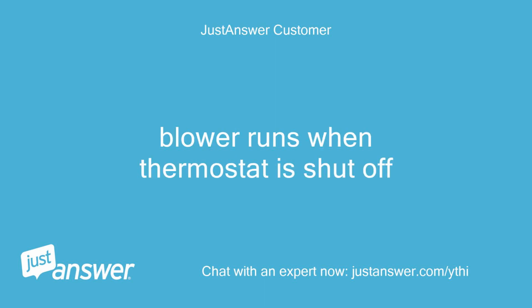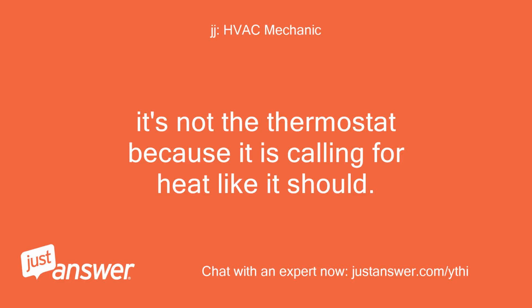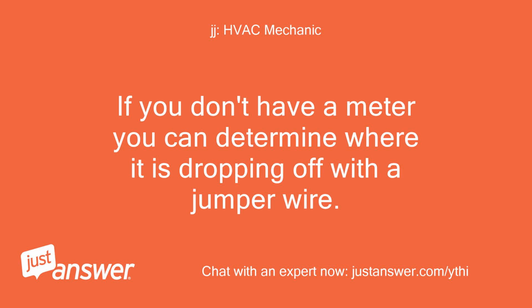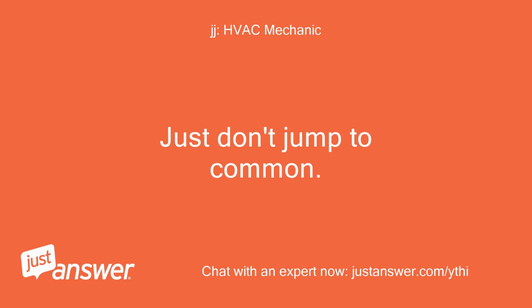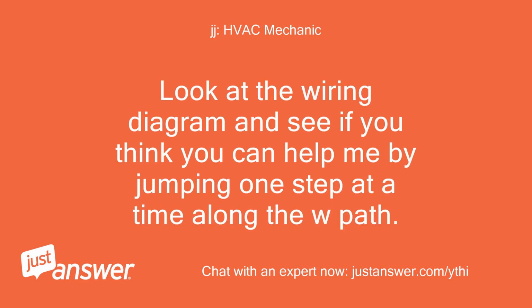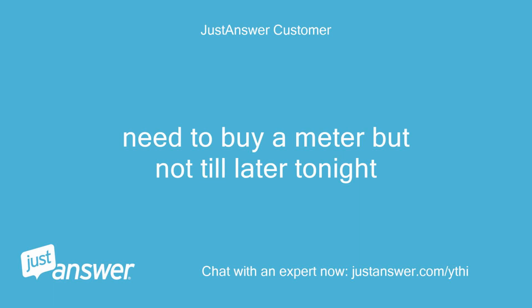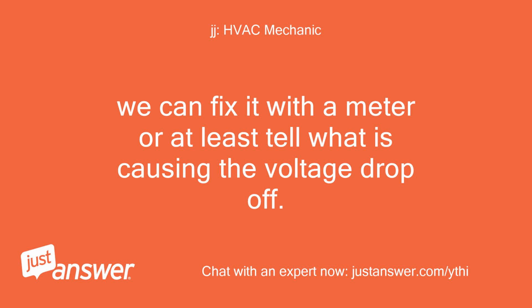Blower runs when thermostat is shut off. It's not the thermostat because it is calling for heat like it should. The power is dropping off of the call for heat. If you don't have a meter, you can determine where it is dropping off with a jumper wire. Just don't jump to common. Look at the wiring diagram and see if you think you can help me by jumping one step at a time along the W path. Otherwise, I will wait while you go buy a meter. Need to buy a meter but not till later tonight. We can fix it with a meter or at least tell what is causing the voltage drop off.